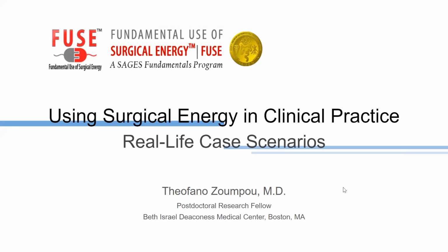Most people start at 30-30 on adults; in pediatrics, you start much lower. Then there are three clinical things you can do: the dwell time, how long you're on the active electrode button; the current density, how much of the tip of the active electrode is actually touching the tissue—the greater the square area of the tip you touch, the less heat you generate; and finally, surgical technique.